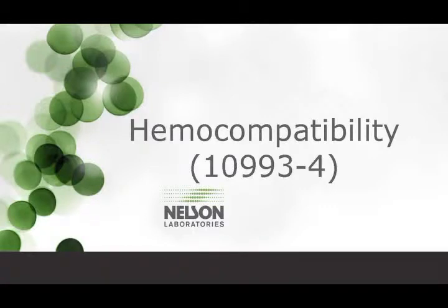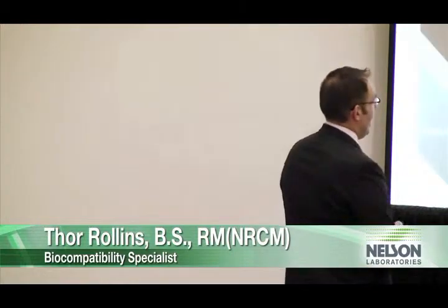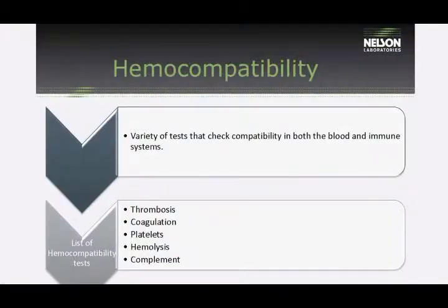So the next category that we're actually changing quite a bit is hemocompatibility. We're still in the middle of changing this standard. So much so that we're going to be meeting in a couple months down in San Diego, and we're probably going to be doing round-robin testing all over again to try to come up with a testing scheme for hemolysis on this. So this is the latest up-to-date information as far as where we're at.